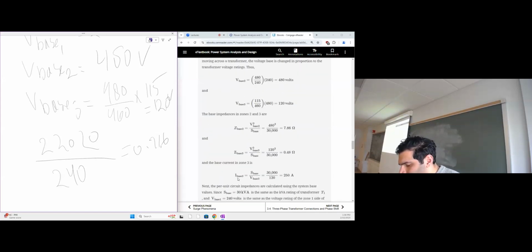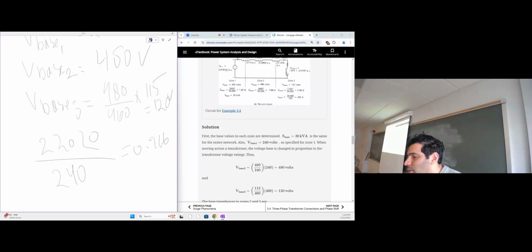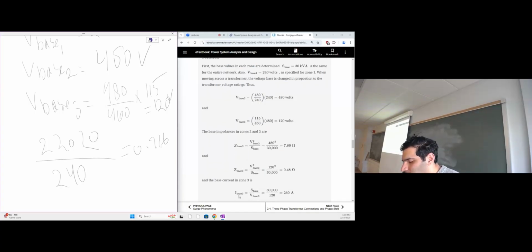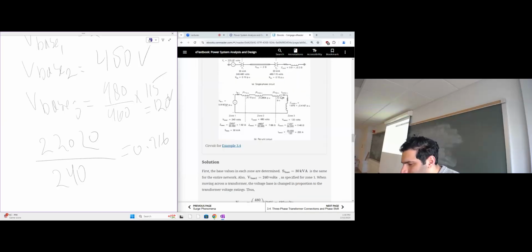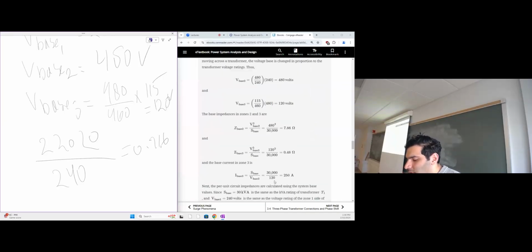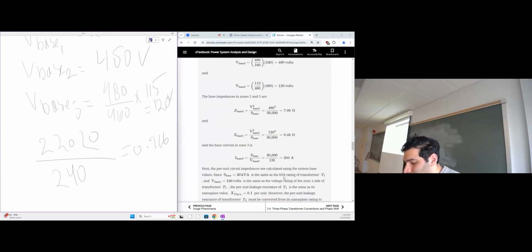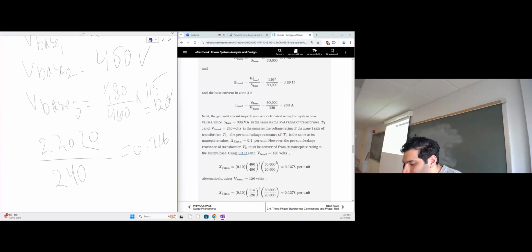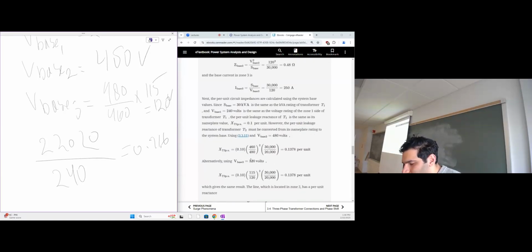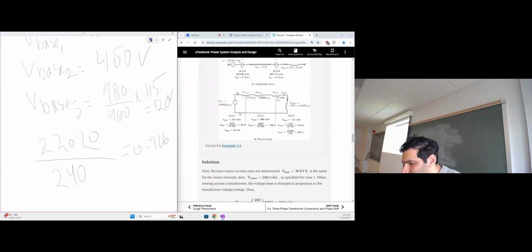The current base, because he's asking about the current in the load. By the end of that calculation and the transformations, we need to determine the current value in per unit and in real values. So we need to know the I base 3 because the load is here. So we divide S by V, it will be 30,000 by 120. And then we need to make sure that our transformer ratings are normalized.